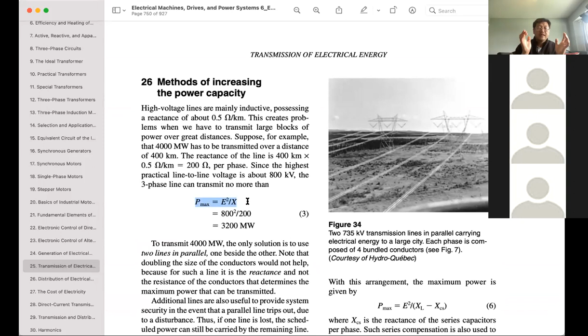So let's do an example. A typical reactance is about 0.5 ohm per kilometer. If we have 400 kilometers - about the distance from Kansas City to St. Louis - and we want to deliver power from Kansas City to St. Louis, what is the total reactance? 200 ohms. What is the maximum power that can be delivered if we use an 800 kV high voltage delivery line? Putting the math together, it will be 3 gigawatts. So the maximum amount of power that can be delivered with current technology is 3 gigawatts.